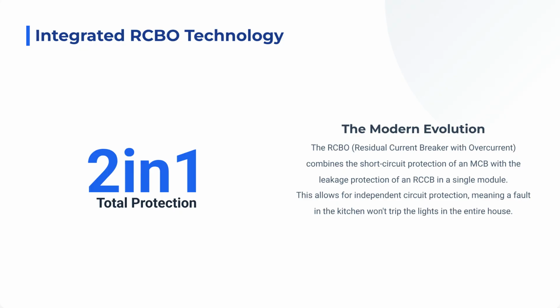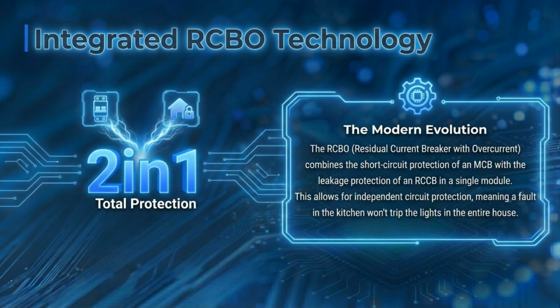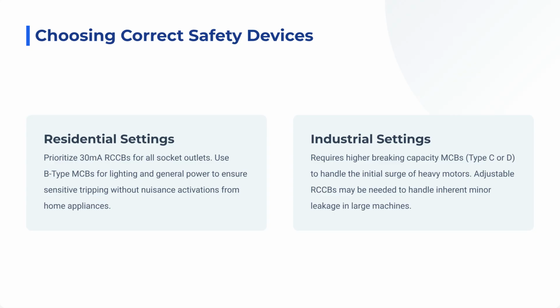The modern evolution brings us the RCBO, a residual current breaker with overcurrent. This two-in-one device combines the protection of an MCB and an RCCB in one module. Integrated RCBO technology allows for independent circuit protection, ensuring a fault on one line does not trip the power for the entire house. Choosing the correct safety devices depends on the setting.